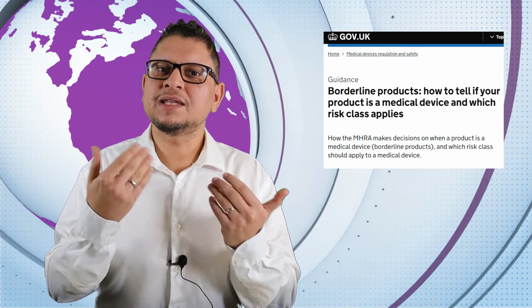Remember that the UK is now out of the European Union, so something that is a medical device in Europe, maybe Annex 16 products, for example, is not in the UK or vice versa, so it can be a bit different. So don't rely just on CE marking. Look at this page and check if your product, which is borderline, is really a medical device in the UK if you want to market your products in the UK.